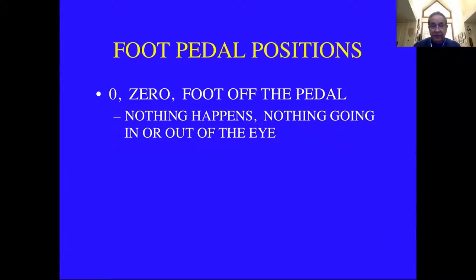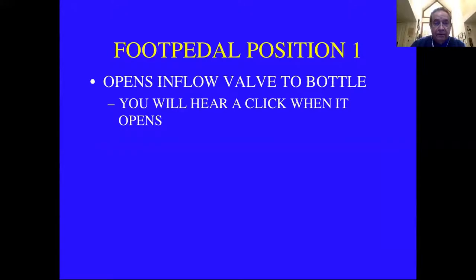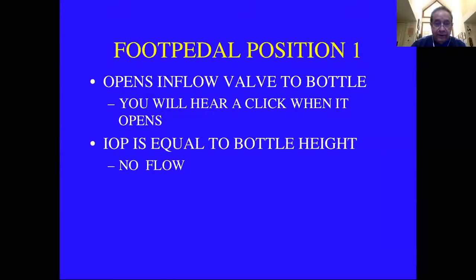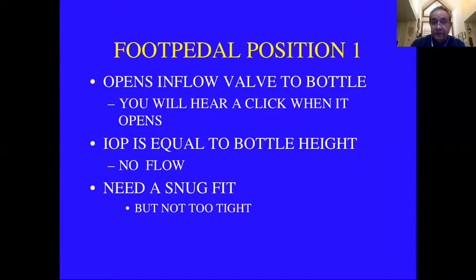In position zero, your foot is off the pedal — nothing goes in or out of the eye. In foot pedal position one, you'll hear a click — that opens the inflow valve to the bottle and lets fluid flow into the eye. Intraocular pressure equals bottle height, but there's no flow through the eye at that point except maybe a little leakage around the tip. You need a snug but not too tight fit, so you need a precise incision size.